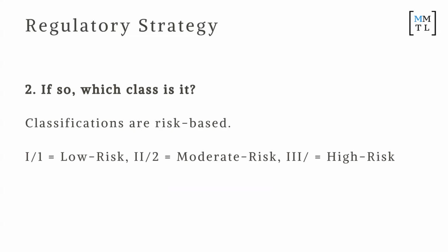This here is a very quick process to get approval, so it takes a few months. This here takes a few years, and this here often takes 5 to 10 years, okay? So it's very long. For example, if you're Elon Musk and you work on Neuralink, you have to know that it will take at least 10 to 15 years to get something approved.